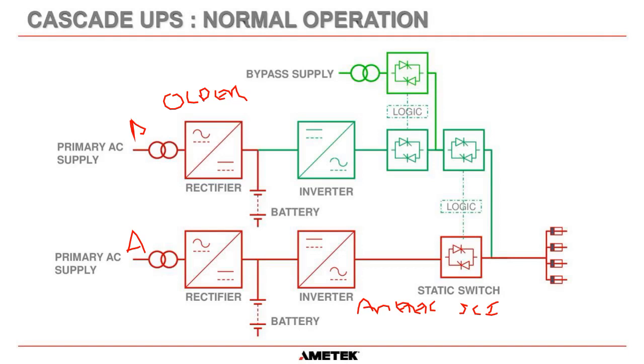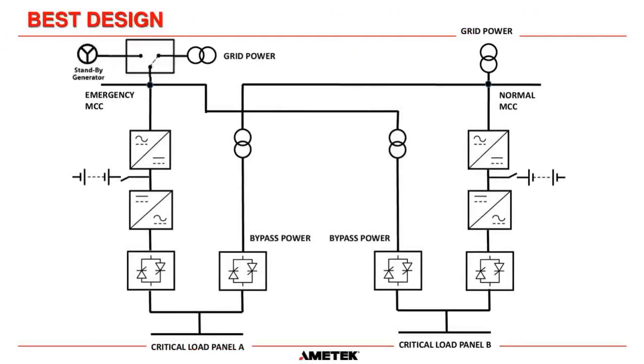But bear in mind, if UPS A is a 30 kVA UPS, then you have to make sure, no matter what the manufacturer is, the other UPS is of the same output rating. Okay. But the next page is the best case scenario for your critical loads. So this is what we would recommend. I hope most of our engineers would recommend this.